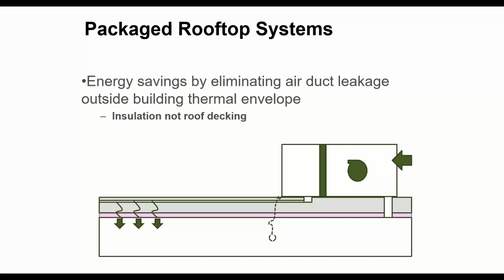So to give you some visuals on that, in this case, we're showing a package rooftop unit. Let me see if I can get the John Madden laser pointer thing going here. So I have outside air coming into my rooftop. I have return air coming back into my rooftop. And then I have my supply duct running down, in this case, through a dropped acoustical type ceiling. I have air leakage that comes into play here. So these are my ducts that I'm actually trying to move air out of.